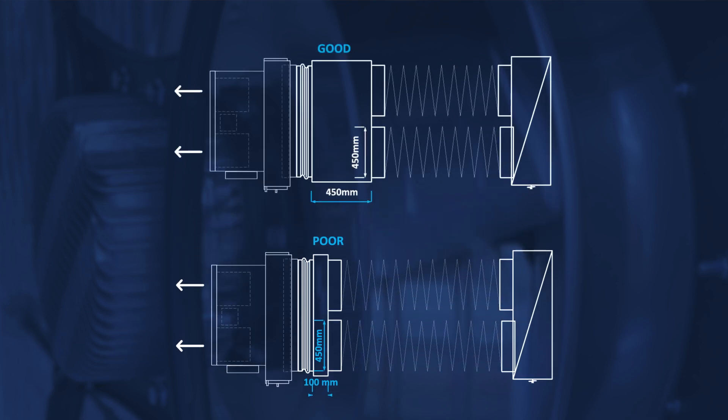As a rule of thumb, the return air plenum should be as deep as the flexible connection is wide. For example, if a 450 millimeter return air flexible duct is used, the return air plenum should also be 450 millimeters deep.